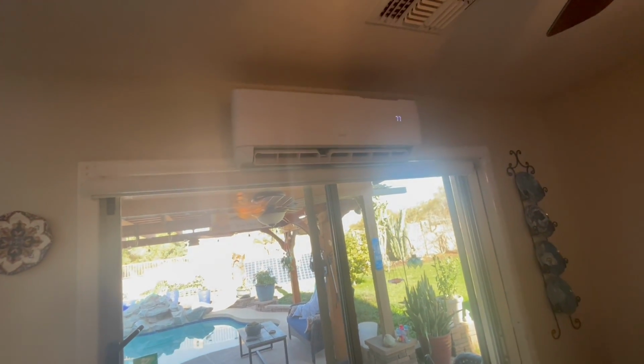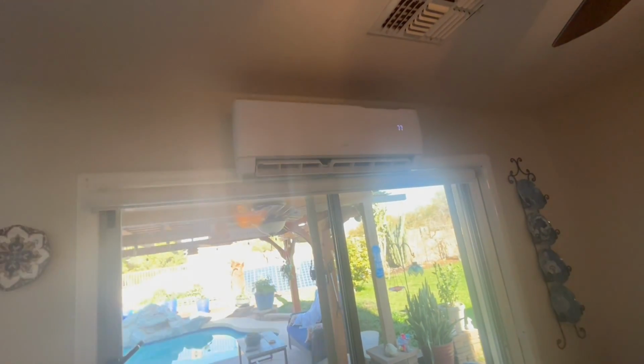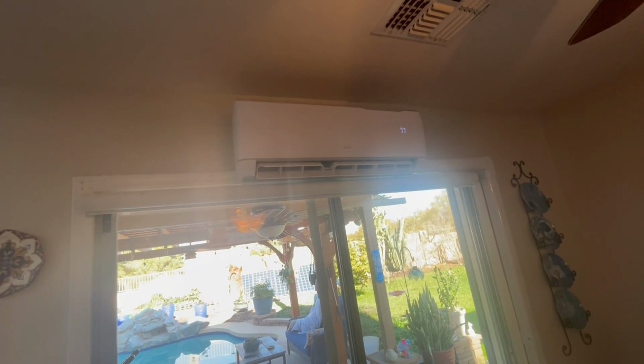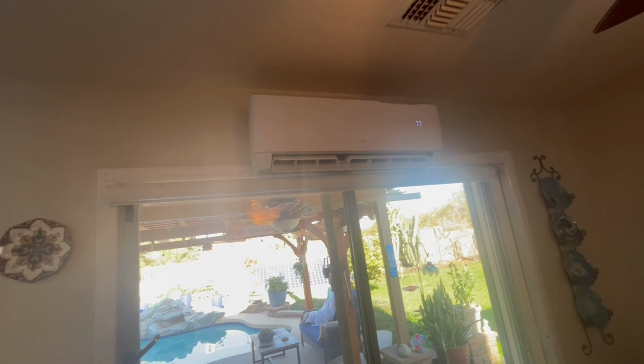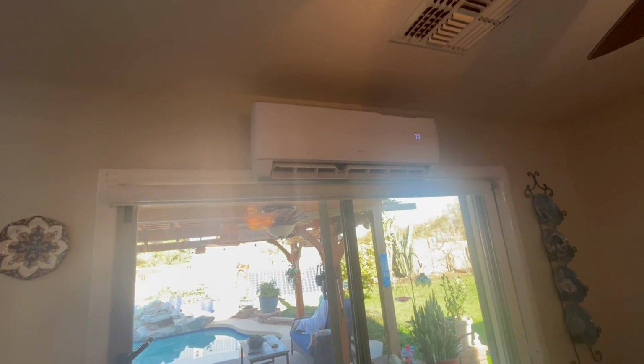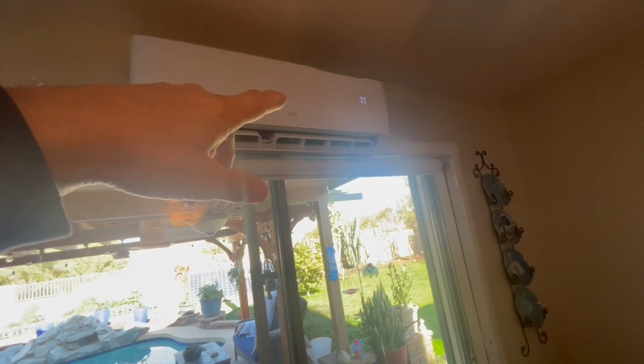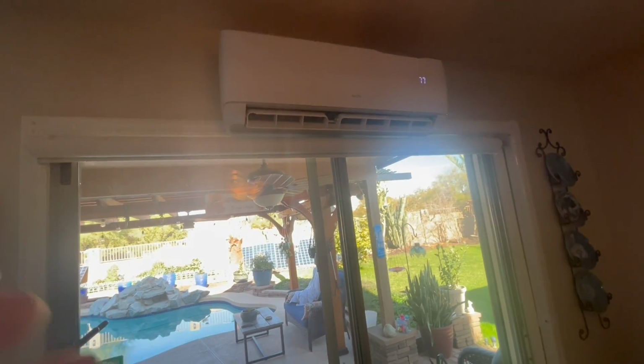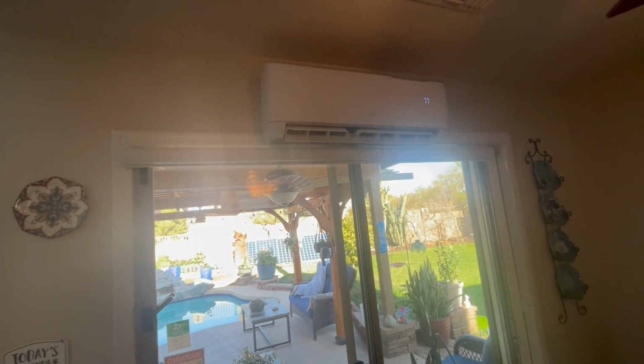But, like I said, when I started running this one, I went like 3 months without running air conditioning or heat. And all of a sudden I went to run this. And it was actually about 32 degrees outside and I got an F1 on it. So I cleaned the screens. I cleaned the temperature sensor on the inside unit, the outside unit, fired it up, but I realized I had to get above 34 degrees outside for this aux to actually work for me.